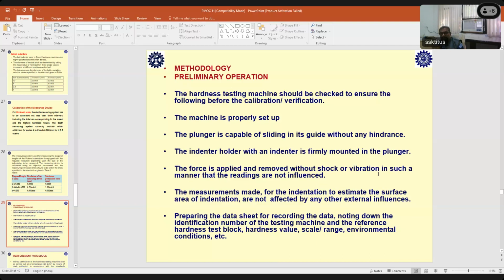Sometimes even in the Vickers machine we use a turret, so there shouldn't be any play, or any vibration or movement in the plunger. The plunger has to move rigidly without any friction, and there shouldn't be any kind of movement in the indenter. The force is applied and removed without shock and vibration, in such a manner that the readings are not influenced. These things look very simple, but they can cause a lot of variation in your measurement. Even for load cell calibration, we always say the force has to be applied without any shock or vibration. Then only you can say the applied force is purely static force, and if there is any vibration or shock, then you will get into a dynamic system. That is not desirable for making a good measurement.